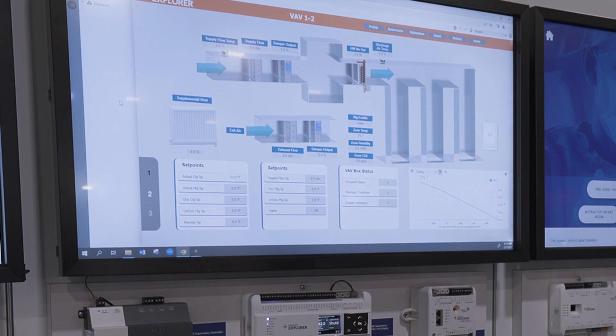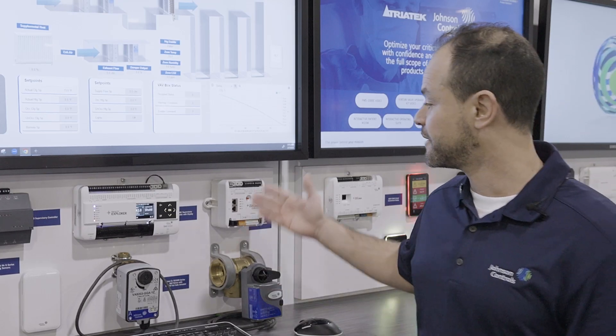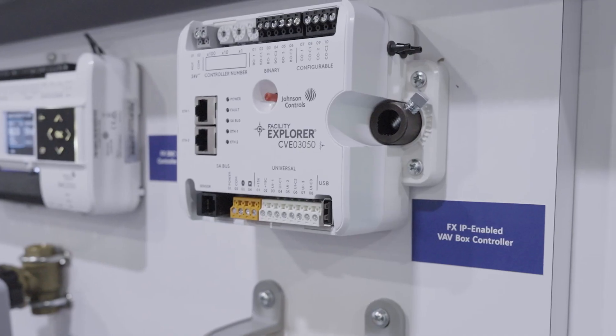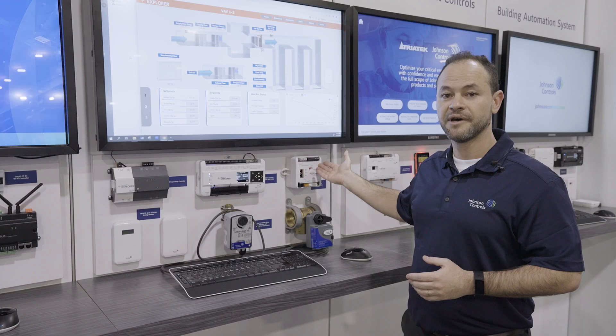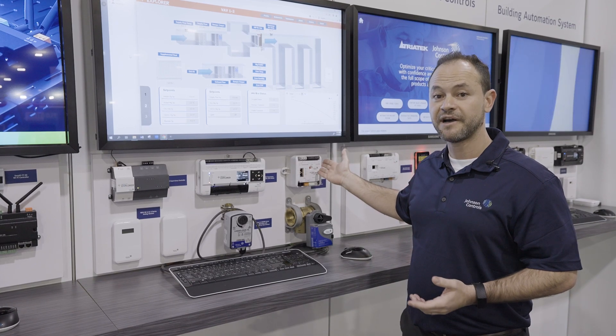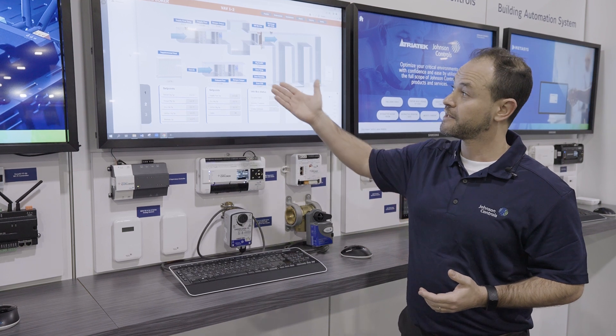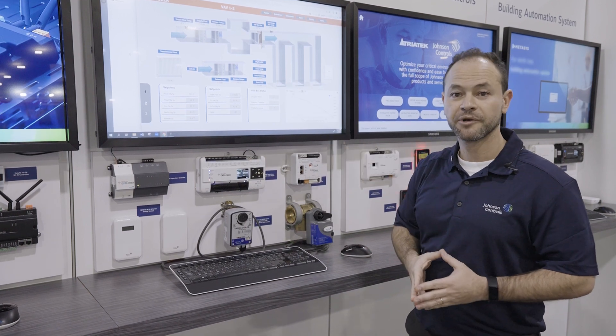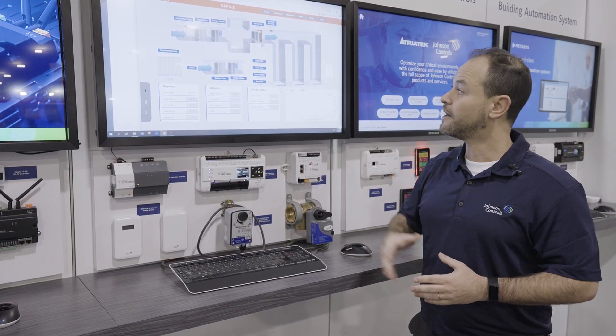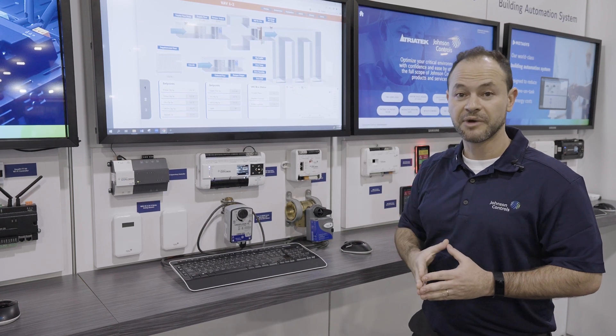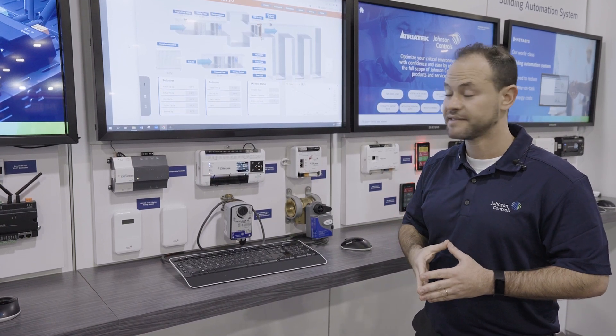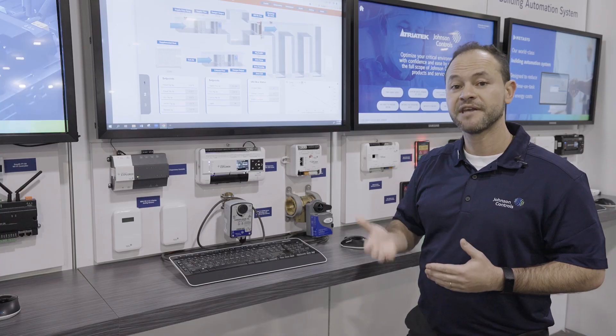Everything here is automatically generated by reading the CAF file in the equipment controller. Once we use the import manager, it reads the CAF file and all the points are automatically imported into the supervisor. All the graphics are set, all the points are bound automatically, and everything is tagged inside the system — giving customers a great head start when building their graphics.